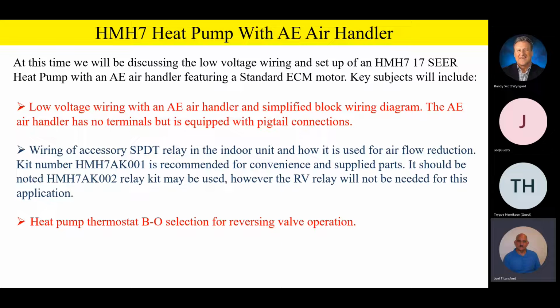Please remember the AE air handler has no hard physical screw terminals, but it's equipped instead with pigtail connections. So just remember there's going to be wire connections on the AE air handler. We're also going to talk about the wiring of the accessory single pole double throw relay in the indoor unit and how it's used for airflow reduction. I want you to wrap your heads around this. When the outdoor unit makes some intelligent decisions on when it needs reduced airflow at reduced capacity, it'll send a signal to a relay inside to reduce the airflow. So we're going to talk about how that works.